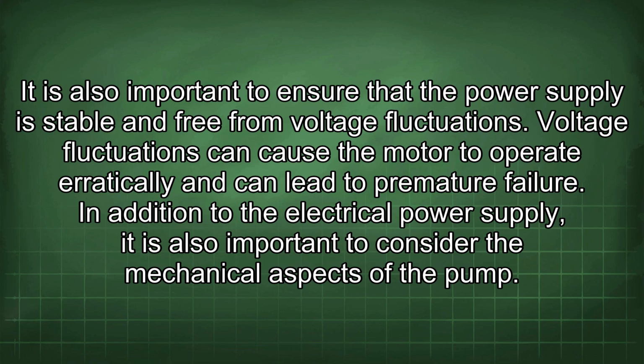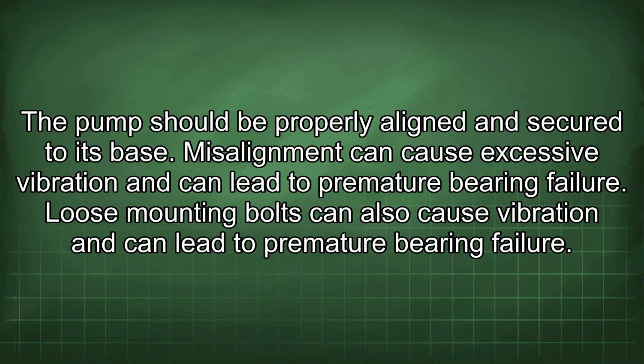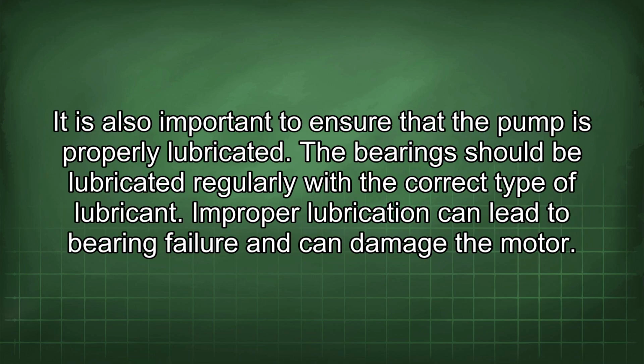In addition to the electrical power supply, it is also important to consider the mechanical aspects of the pump. The pump should be properly aligned and secured to its base. Misalignment can cause excessive vibration and can lead to premature bearing failure. Loose mounting bolts can also cause vibration and can lead to premature bearing failure. It is also important to ensure that the pump is properly lubricated. The bearings should be lubricated regularly with the correct type of lubricant. Improper lubrication can lead to bearing failure and can damage the motor.